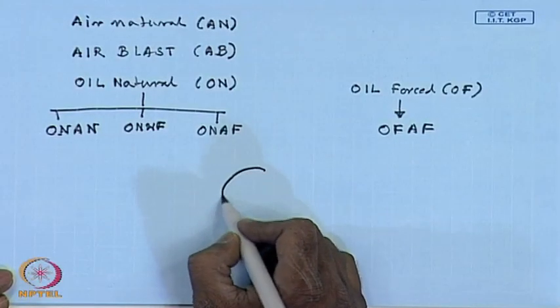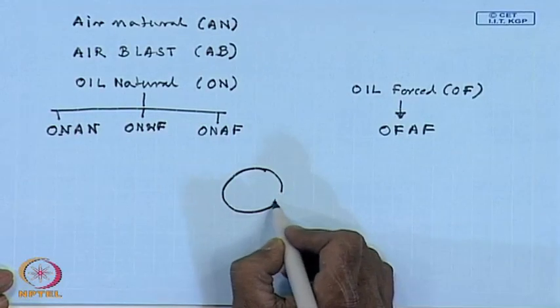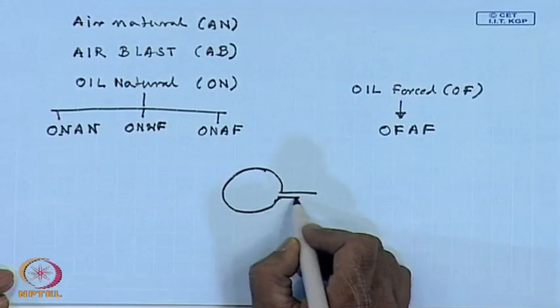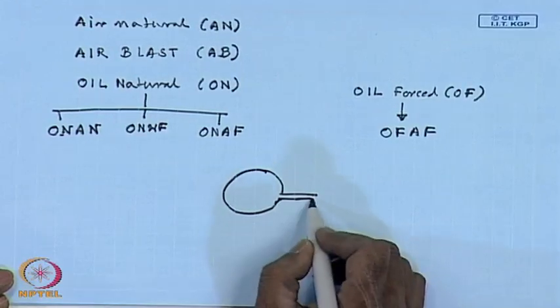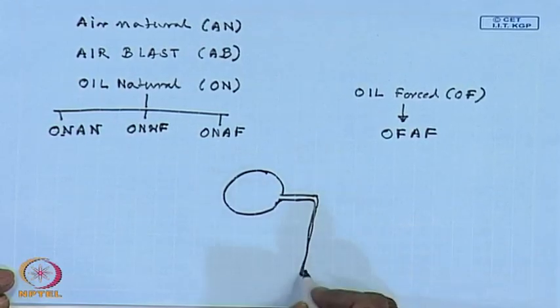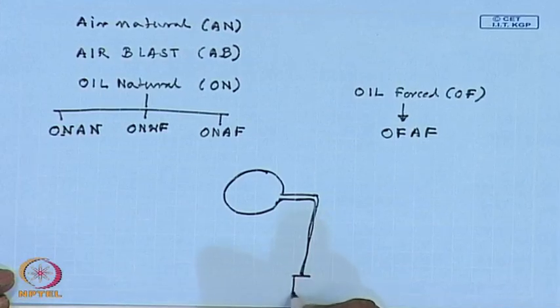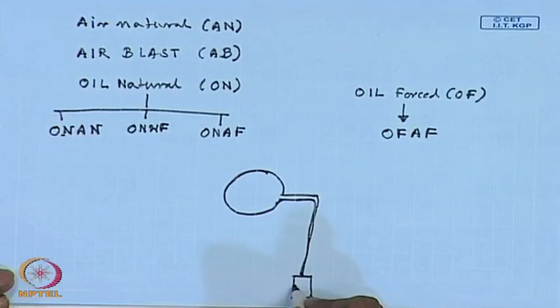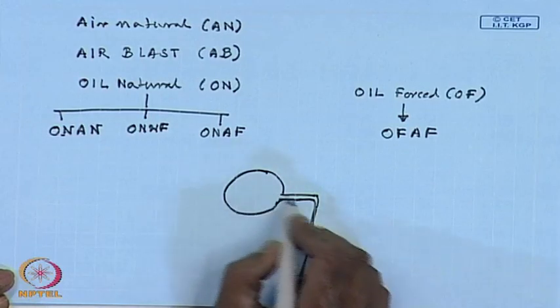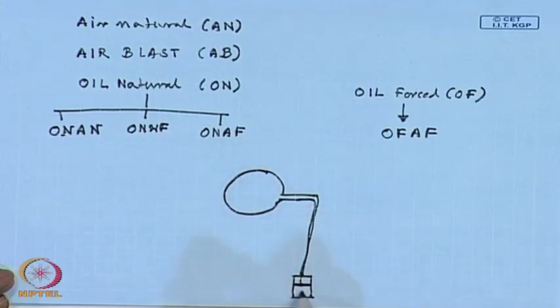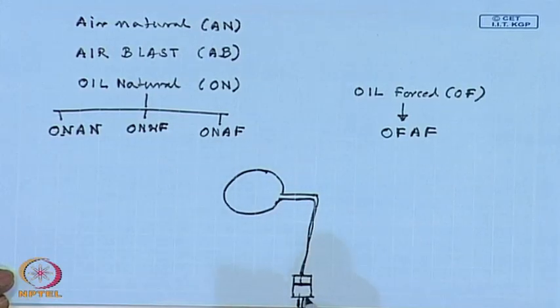So, this is the conservator. The conservator will normally have a pipe extending down. This is called the breather, and at the breather end there will be a cylinder like this. This cylinder will contain silica gel, so that the air that comes in or out of the conservator always passes through this silica gel, which absorbs moisture. So, the contamination of the transformer oil due to atmospheric moisture in the air is minimized.